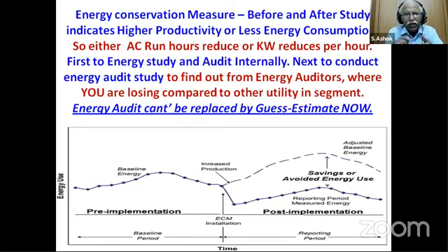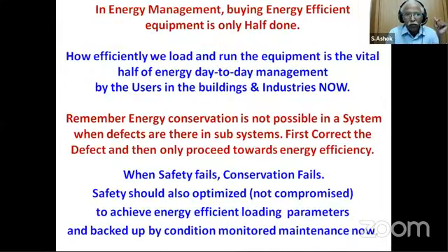Don't do guesswork and estimating the energy. This can be this much, this can be this much. The power factor is always at 0.9. It is not happening. The power factor is almost at 0.5 or 0.6, when the blower is loaded at only 50%, or the pump is loaded at 50%. This is happening. So let us try to reduce the kVA of a given AC consumer. Let us try to reduce the kWh or the energy bill of the given consumer.